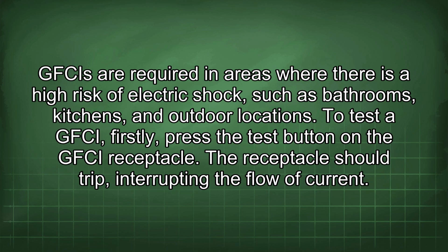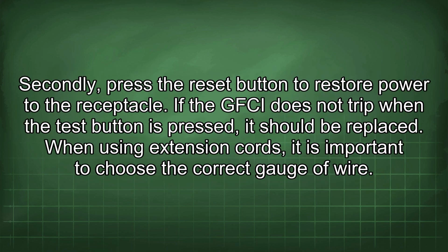To test a GFCI, firstly, press the test button on the GFCI receptacle. The receptacle should trip, interrupting the flow of current. Secondly, press the reset button to restore power to the receptacle. If the GFCI does not trip when the test button is pressed, it should be replaced.